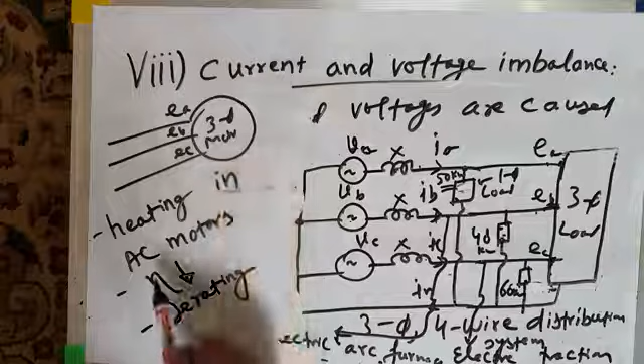And if you want to control the heating or temperature rise, you have to derate your motor. So that results in derating of the motor. That means if the motor was designed for 1000 horsepower, you have to run it at less than 1000 horsepower in order to control the heating. So therefore, three-phase unbalanced voltages fed to three-phase induction motors or three-phase synchronous motors result in large heating of the motors, which reduces the efficiency, and hence you may have to go for derating of these motors.